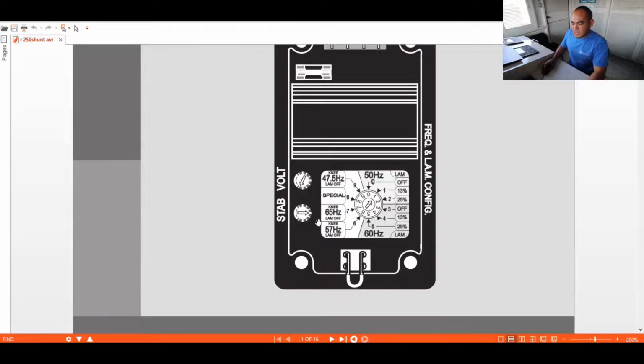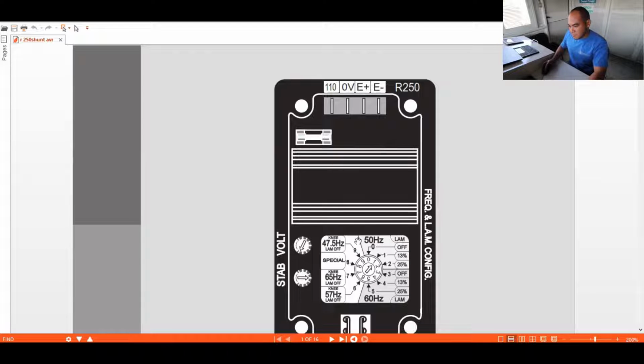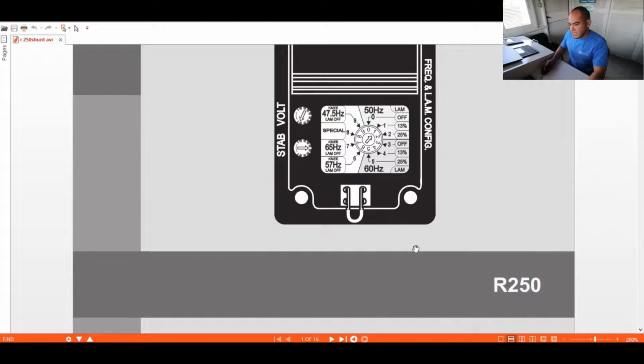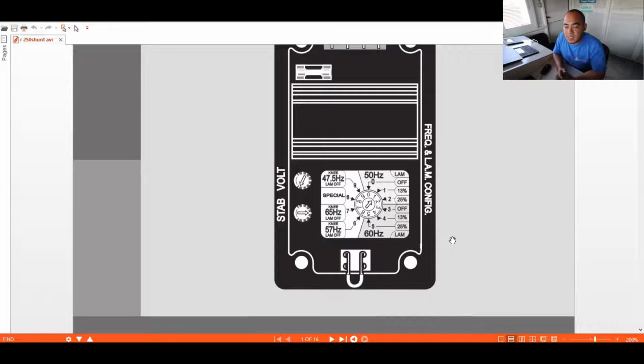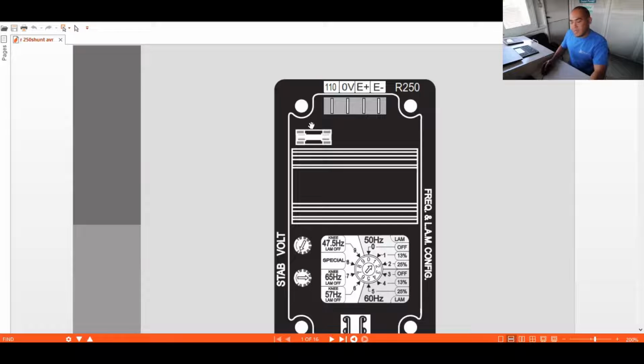So I'm talking about what the LAM is. I will give you the meaning: LAM is the load acceptance module. That is the meaning of the LAM. At the top here, let's go back to the R250. We have the sensing voltage of 110 to 0, and you have the exciter field positive E and negative E. These are the connections where you can connect your exciter field.